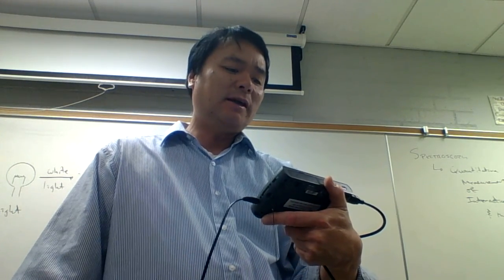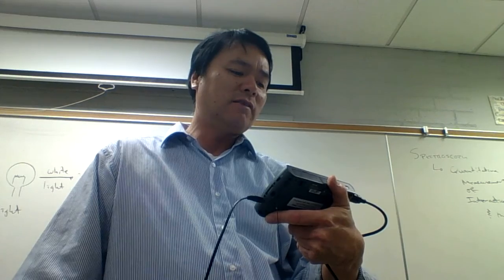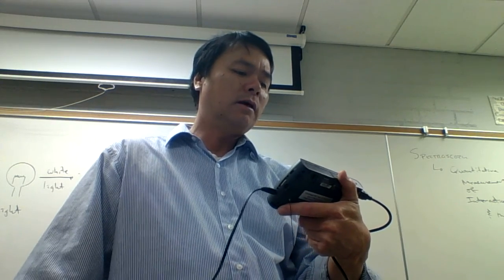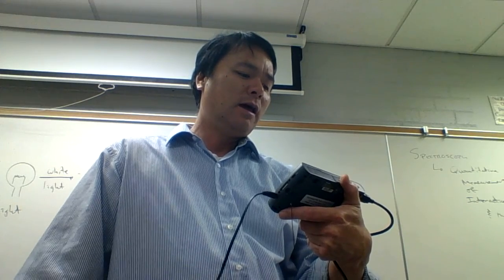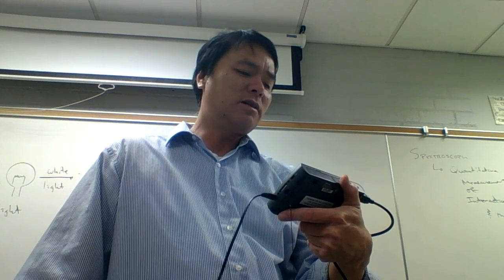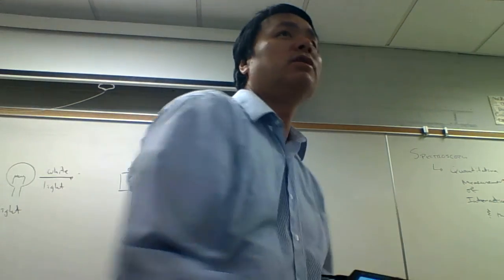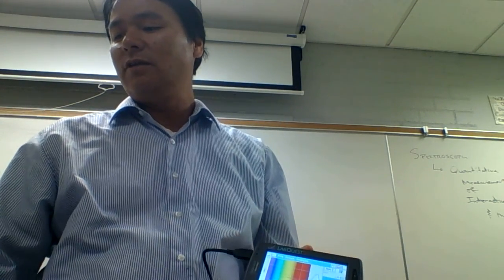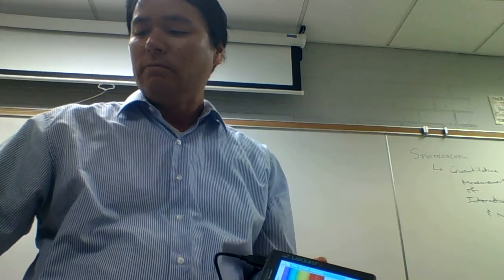All right, now keep an eye on that peak. What you want to do is look at the visible. The visible kind of peaks out in the orange and the red. Take a look at the units there. It's close to 0. Now I'm going to flip the cuvette to put the grooves the other way. So rotate the cuvette 90 degrees and see what happens.